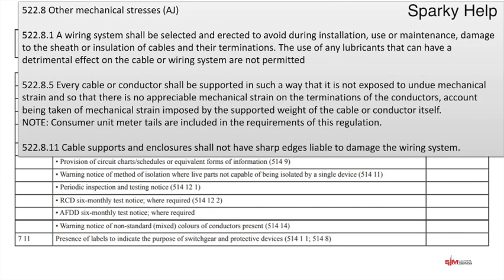So what are we looking at here? It says a wiring system shall be selected and erected to avoid, during installation, use or maintenance, damage to the sheath or insulation of cables and their terminations. The use of any lubricants that can have a detrimental effect on the cable or wiring system are not permitted. Every cable or conductor shall be supported in such a way it is not exposed to undue mechanical strain, and so that there is no appreciable mechanical strain on the terminations of the conductors, account being taken of mechanical strain imposed by the supported weight of the conductor itself.